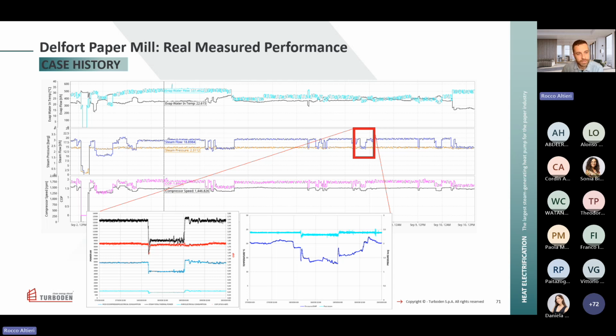On the last part of this period, of stop of one of the paper machines, you see that when the paper machine was started up again, the request from the customer was to supply again the nominal steam value. And also here, the heat pump was able to go to the max load in less than 20 minutes, so it was approximately 15 minutes. So in a few minutes, you see that we can adapt very quickly to the steam demand.